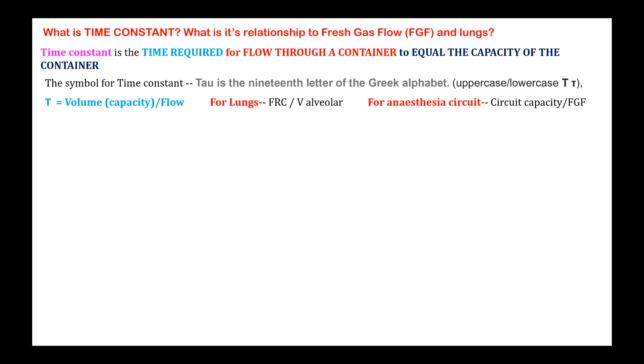Before starting anesthesia, what does the circuit contain? Room air, sir. Room air. That has to be removed and filled up with the anesthetic gases that you are giving, oxygen, nitrous oxide, and your inhalation agent, or oxygen, air, and inhalation agent, whatever you are using. It is just like priming your cardiopulmonary bypass circuit. The same way, you have to remove all the air, or make the patient inhale all the air, and then fill up that whole circuit with the agents that you want to deliver and achieve the partial pressure in the alveoli at a faster time. Okay, so that is the importance of this time constant.